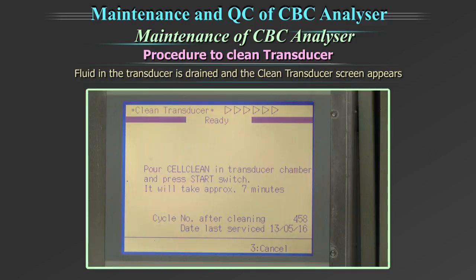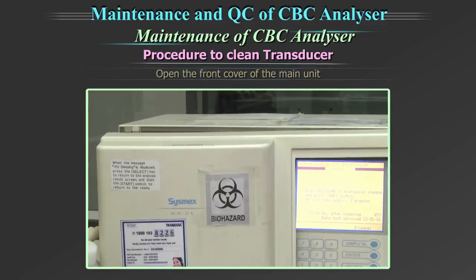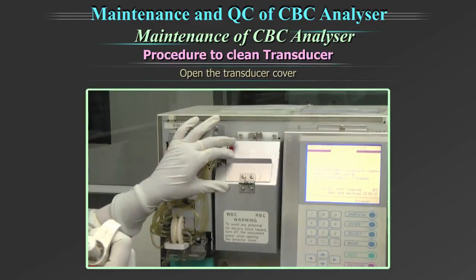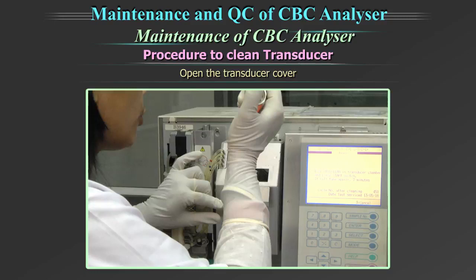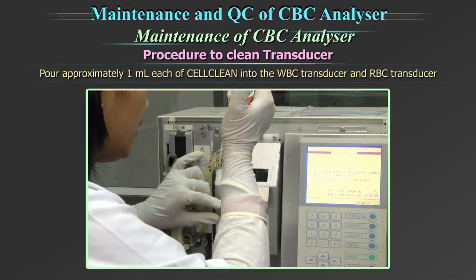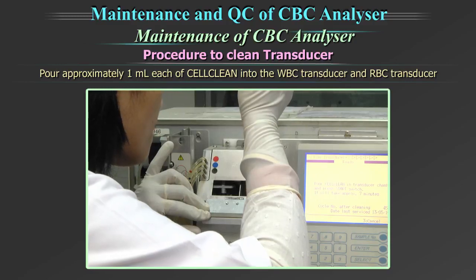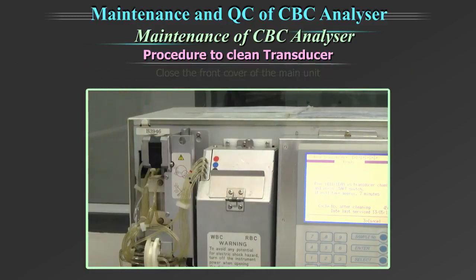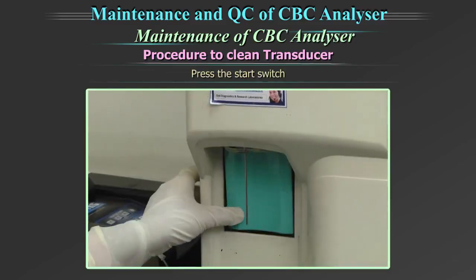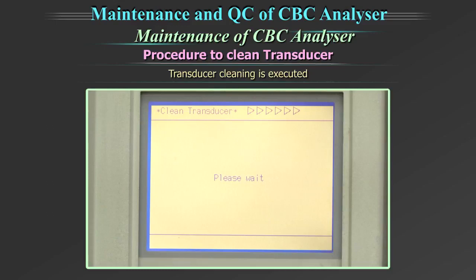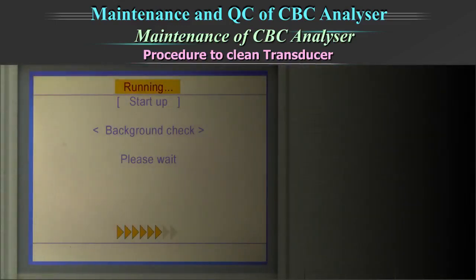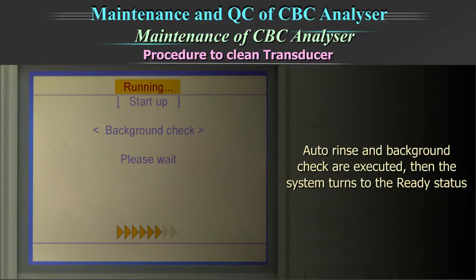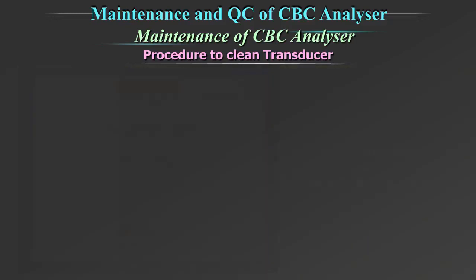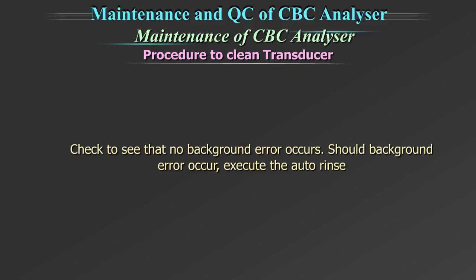Fluid in the transducer is drained and the clean transducer screen appears. Open the front cover of the main unit. Open the transducer cover. Using the filler provided by the unit, pour approximately 1 ml each of cleaning solution into the WBC transducer and the RBC transducer. Close the transducer cover. Close the front cover of the main unit. Press the start switch. The transducer cleaning is executed. When the transducer cleaning is completed, the auto rinse and background check are executed and the system turns to the ready status. Check to see that no background error occurs. Should background error occur, execute the auto rinse.